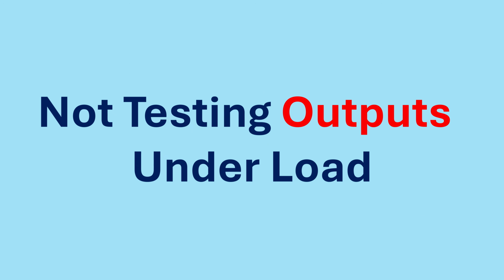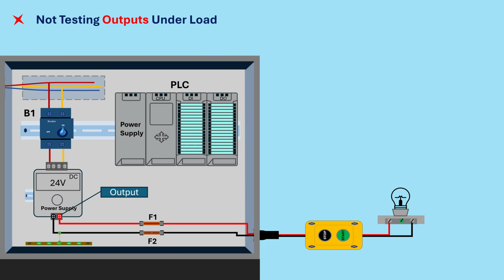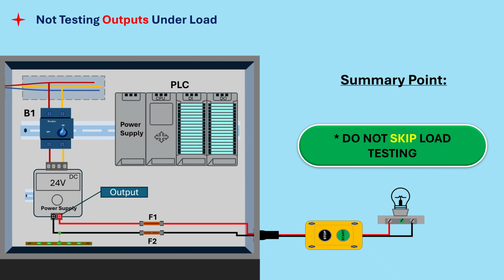Mistake number 9. Not testing outputs under load. An output can look perfect on a meter or indicator light, yet fail the moment it has to drive a solenoid, a motor starter coil, a valve, a lamp, or any real device that draws current. When a device is under load, weak wiring, bad terminals, failing transistors, or undersized power supplies reveal themselves. Don't skip load testing, is the summary point from mistake number 9.